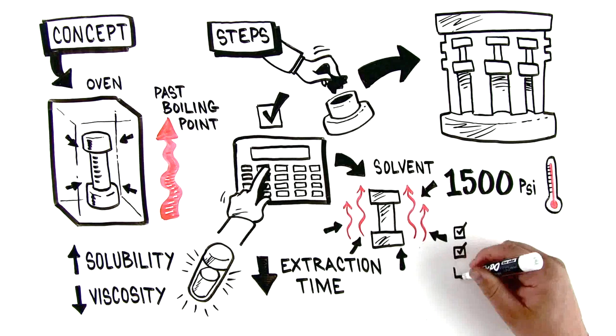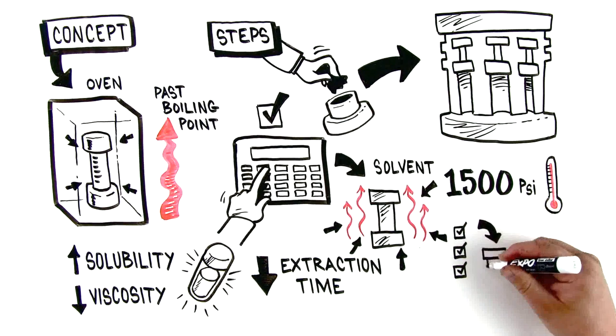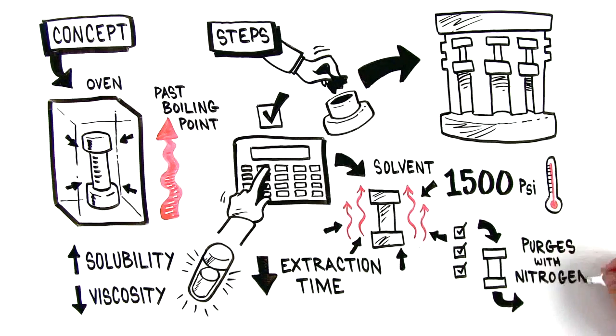Next, the sample can be allowed to sit exposed to solvent for a predetermined amount of time. This is referred to as a static extraction. Once the static extraction is complete, the system pumps fresh solvent through the cell and pathway and purges with nitrogen.